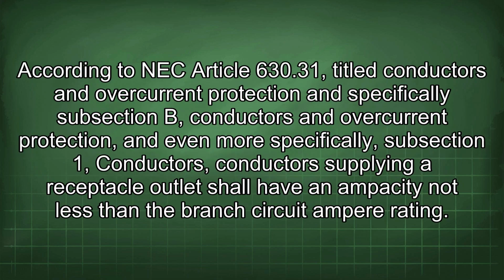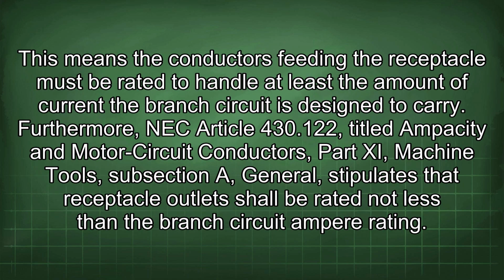According to NEC Article 630.31, titled Conductors and Overcurrent Protection, and specifically subsection B, Conductors and Overcurrent Protection, and even more specifically subsection 1, conductors supplying a receptacle outlet shall have an ampacity not less than the branch circuit ampere rating. This means the conductors feeding the receptacle must be rated to handle at least the amount of current the branch circuit is designed to carry.